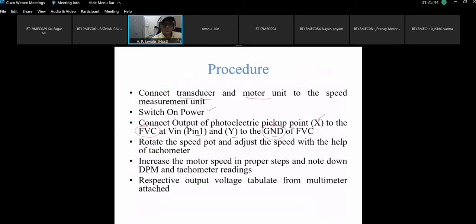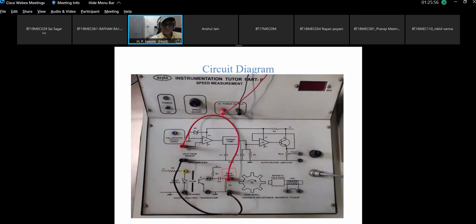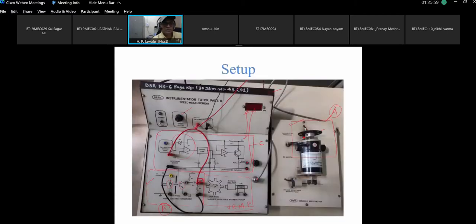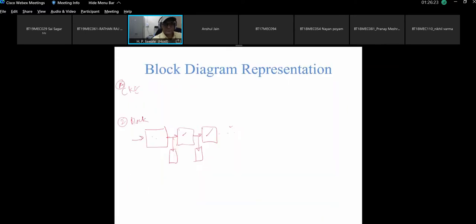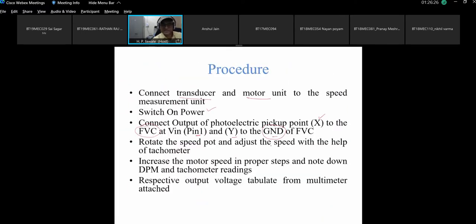So coming back to the procedure: rotate the speed pot and adjust the speed with the help of the tachometer. We have a speed adjustment knob here. As we increase this, the magnified signals are given to the motor so that a larger voltage gives the speed from 0 to the full speed of the motor. So through the speed adjustment we vary the speed from 0 to the rated higher speed. That is what is told in the procedure, and adjust the speed with the help of the tachometer.